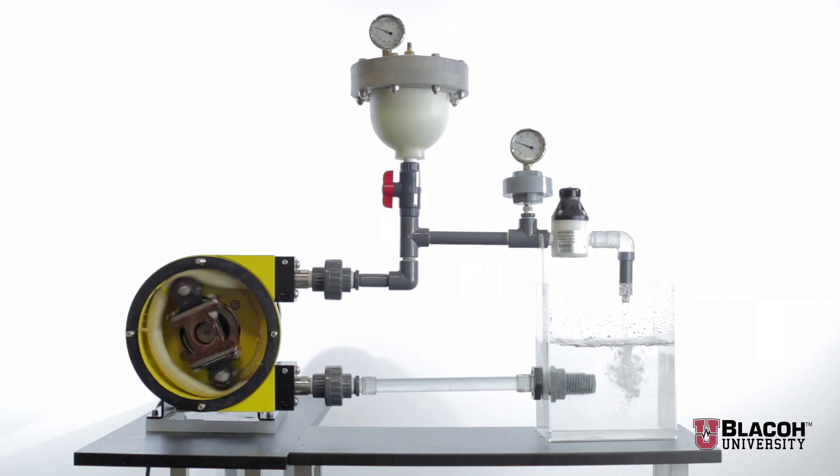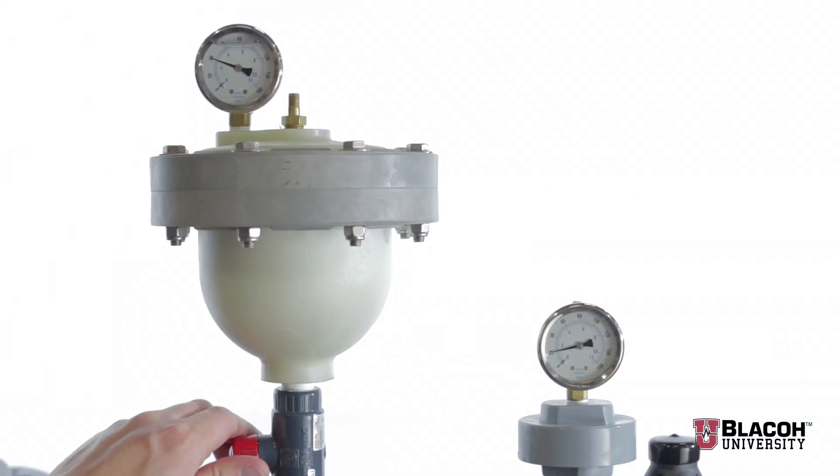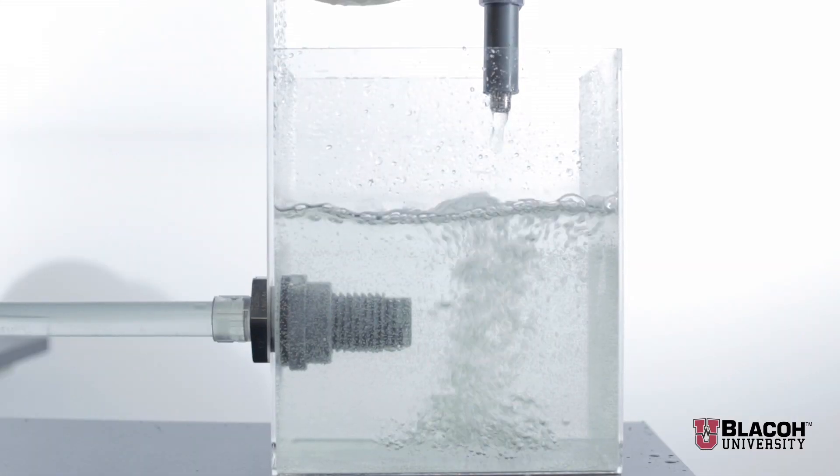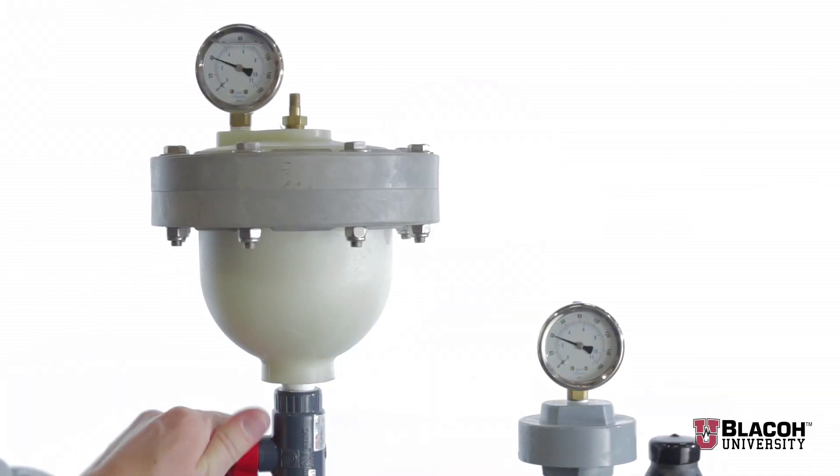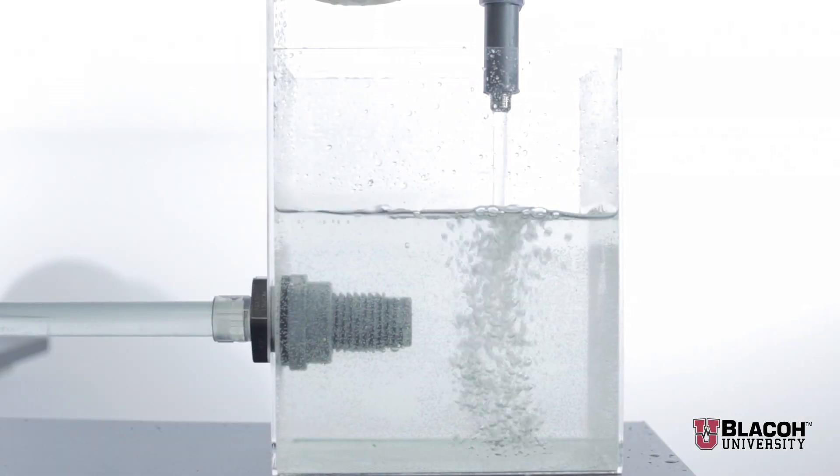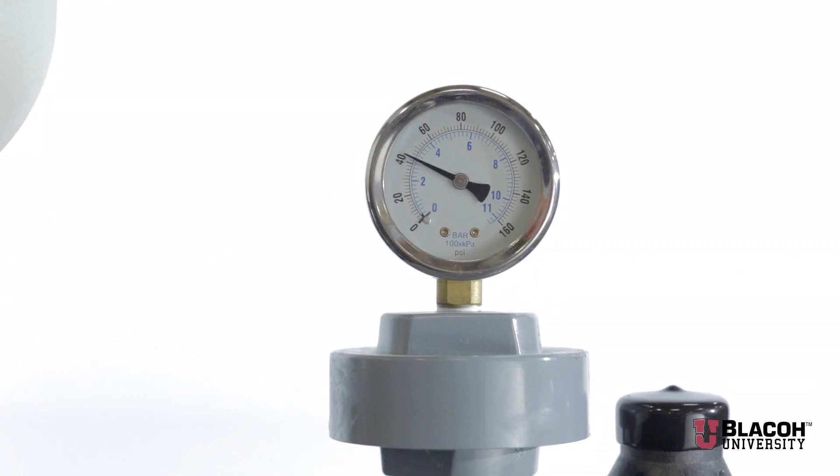And again, as we deactivate the dampener you will see the pulsation and the wide variation in pressure. Activating the dampener again immediately smooths the flow and eliminates the wild pressure swings.